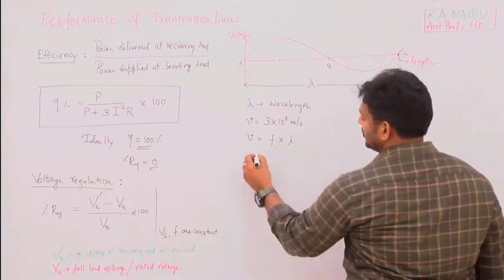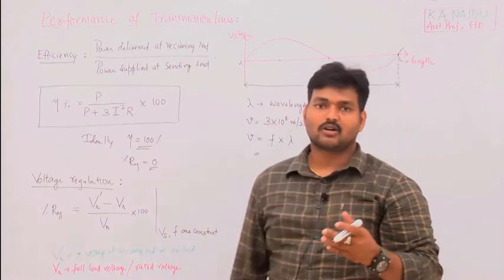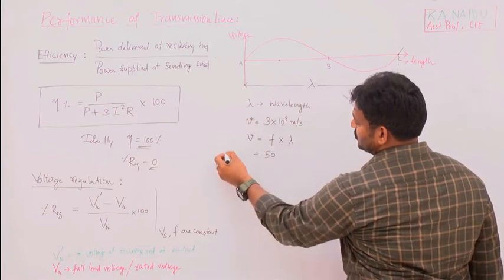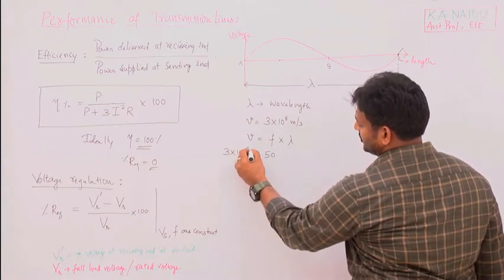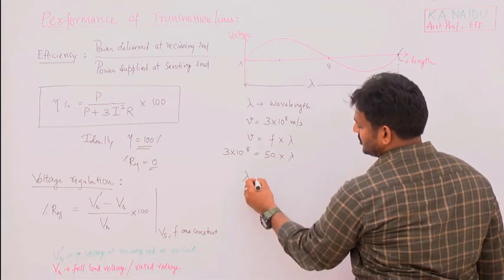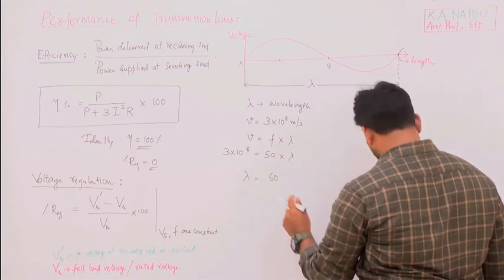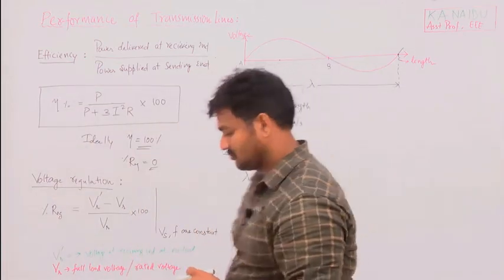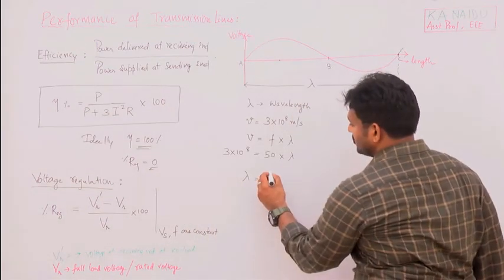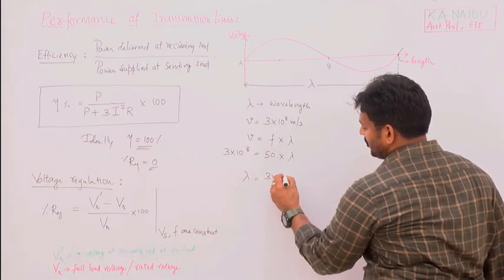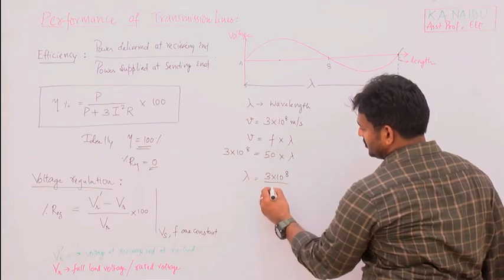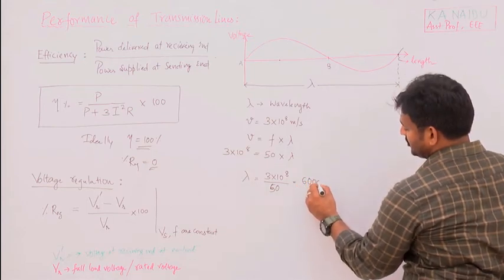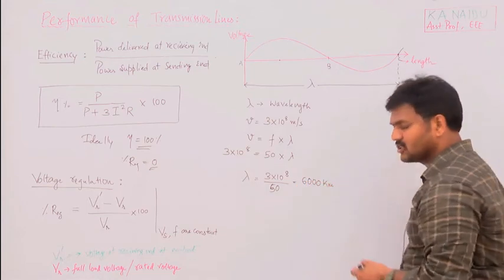In India, we have a constant frequency of 50 Hz. Substituting: 3×10⁸ = 50 × λ, therefore λ = 3×10⁸ / 50 = 6×10⁶ meters, which equals 6000 kilometers. So the wavelength of the travelling wave on a transmission line at 50 Hz is 6000 kilometers.